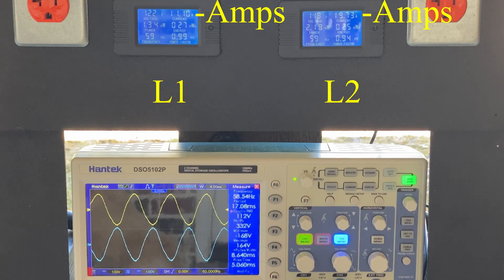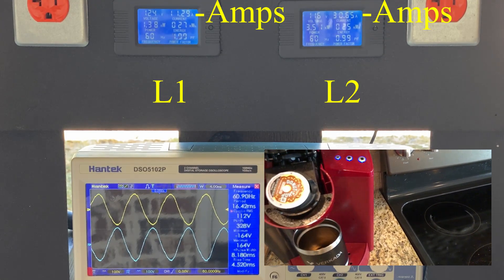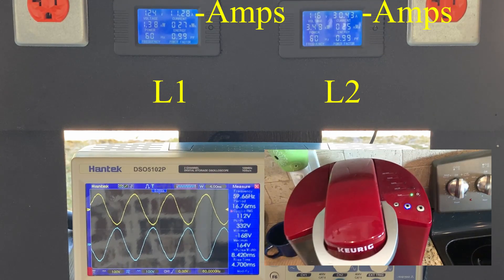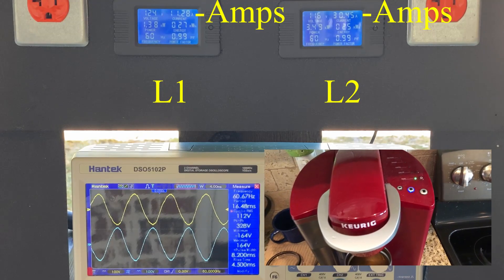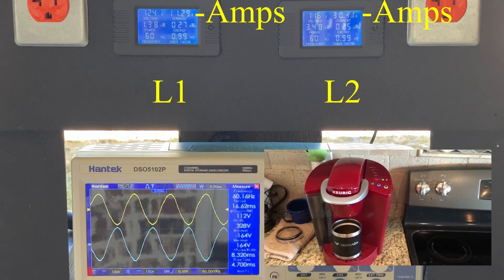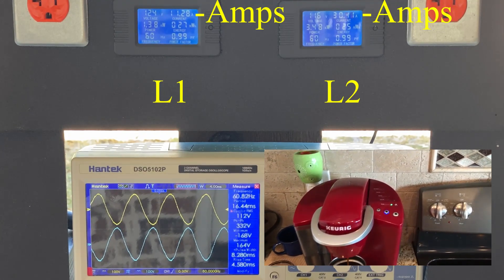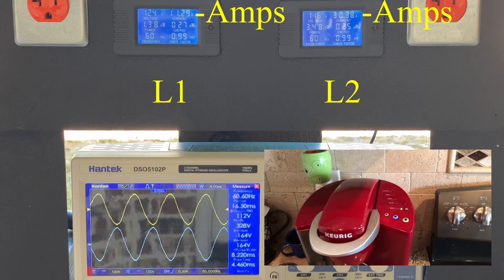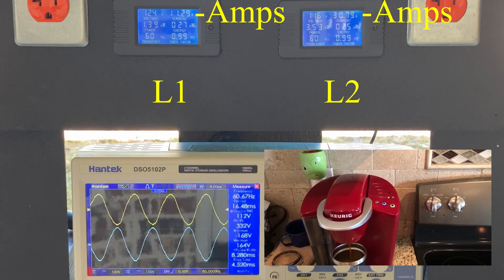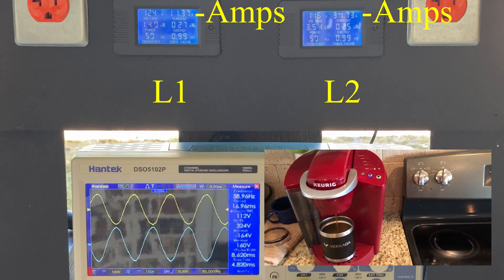It produces 240 volts by adding two 120-volt legs together that are perfectly synced and 180 degrees out of phase. Each leg is capable of half the max generator output — in this case, 4200 watts continuous. The generator cannot produce all 8500 watts on one leg; if you tried, it would either trip the breaker or burn the generator head up. I'm loading the L2 leg to the max, showing about 41 amps at peak, and at this point the sine wave has cleaned up pretty well.